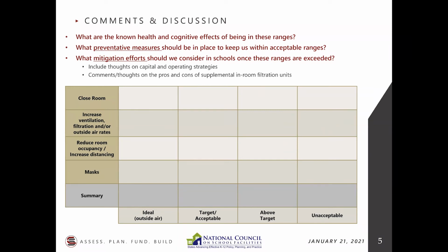When we look at criteria related to air cleaners in a standard realm, we look at an 80% reduction. When you see room size on an air cleaner, that means that before you put it into the new equilibrium that you're going to reach, you get an 80% reduction in particulate. You may not reach that if you don't have the size limitation. You're not matching it directly to the size. Say, for instance, your classroom is 700 square feet and it recommends this is good for 450 to 500. You may not get an 80% reduction, but you may get a 60% reduction. That's still significant. That's still worthwhile looking into.